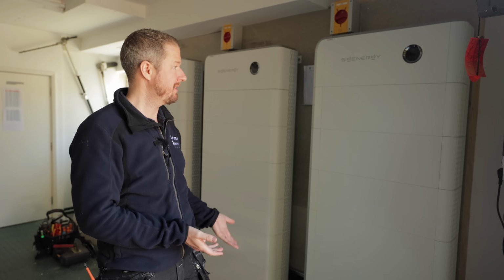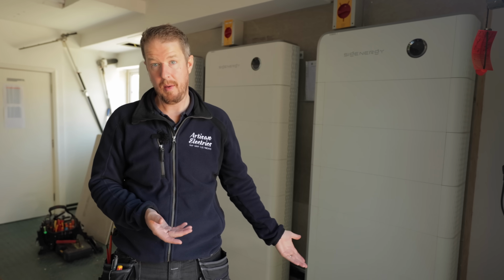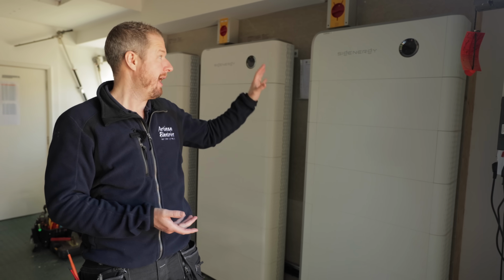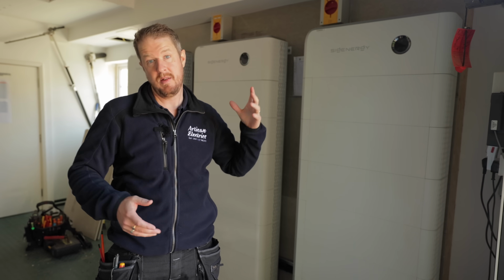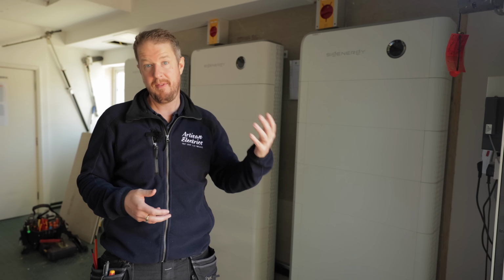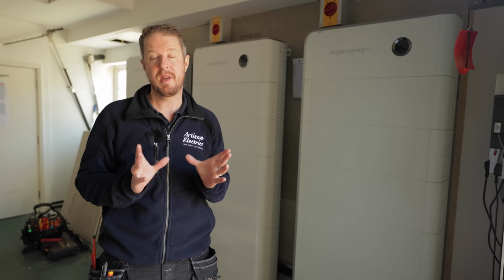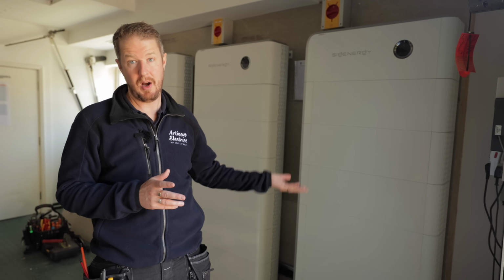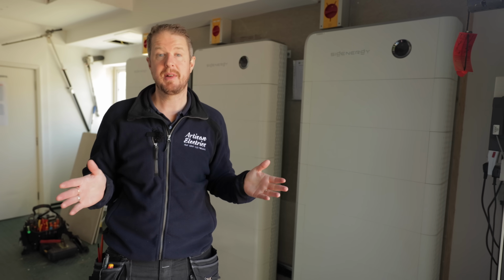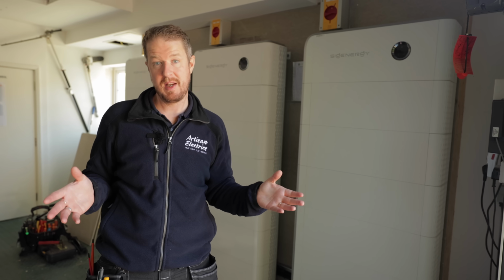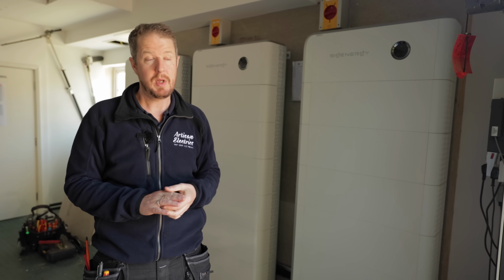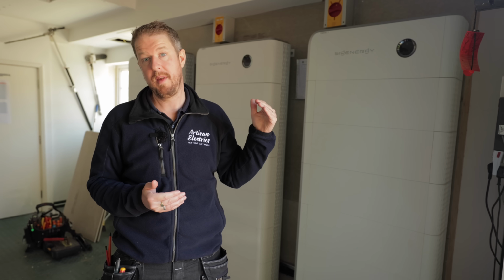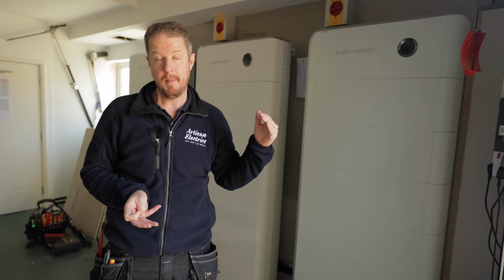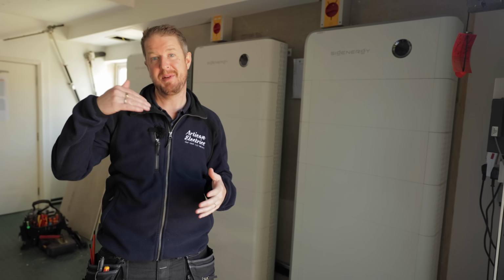For example, these stacks of 48 kilowatt hour battery systems have a 15 kilowatt inverter in. So if you take 48, divide it by 15, that gives us about 3.2 hours to fully charge these batteries. That's absolutely fine because the customer has a 5-hour cheap energy window. But we could even go slightly smaller on the inverters if we wanted to, but it all depends on what their maximum demand is as well.